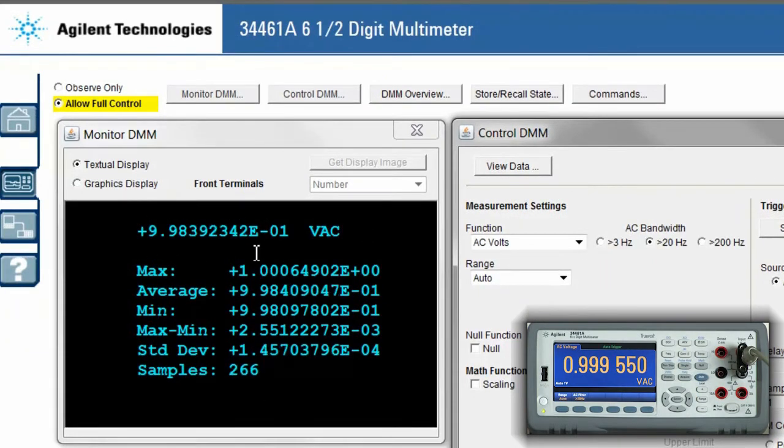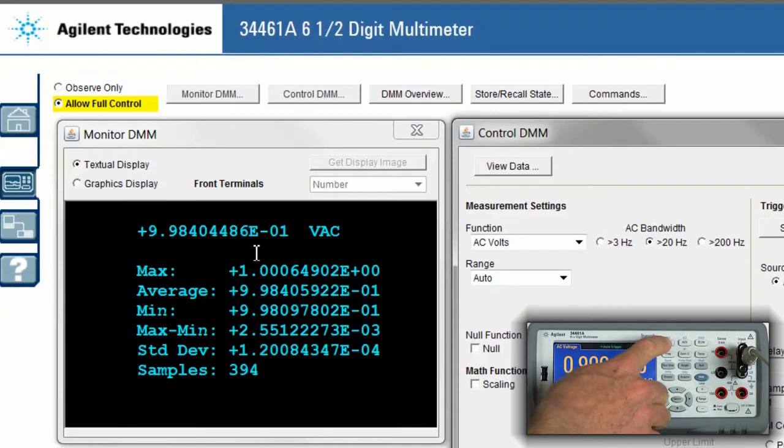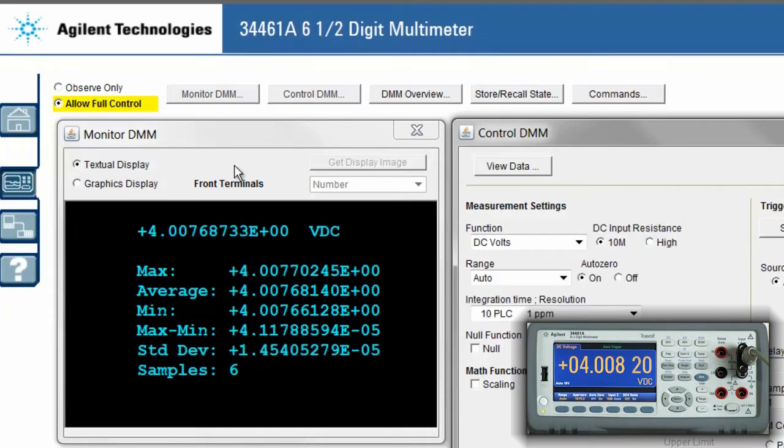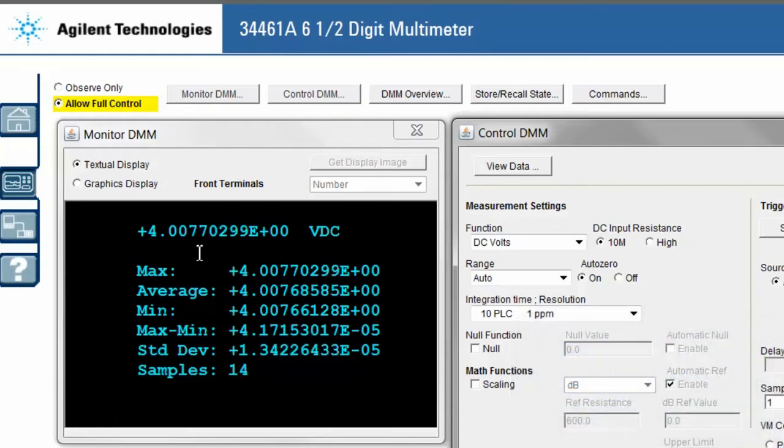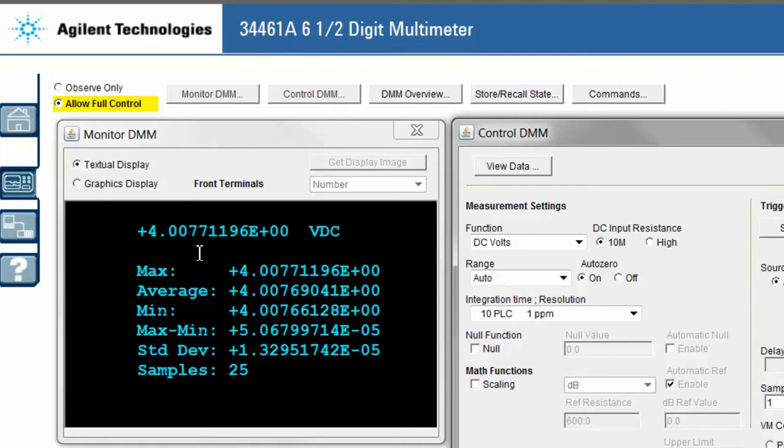We can see the web UI is updated with the front panel of the instrument. I'm going to go ahead and switch back the front panel of the instrument, and again the web UI is updated. As you can see, we have a signal that's a 4 volt DC signal with some AC ripple riding on top of it.